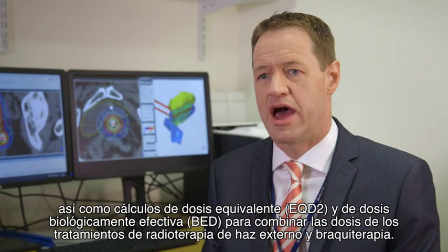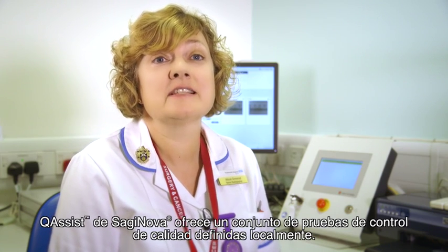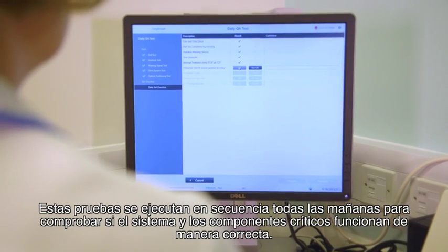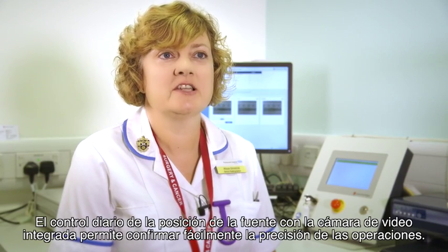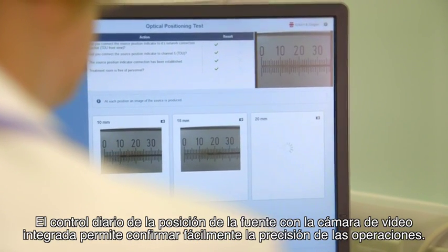The system also provides EQD2 and BED calculations to combine external beam and brachytherapy doses. With QAssist from SagiNova I have a set of locally defined quality assurance tests. These are performed in sequence each morning to verify whether the system and critical components are operating correctly. The daily source position check with integrated video camera allows easy confirmation of accuracy of the operation.